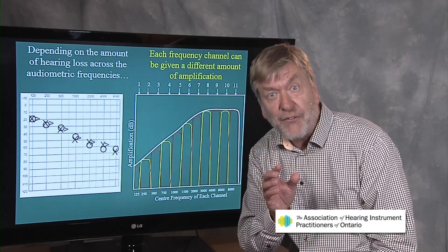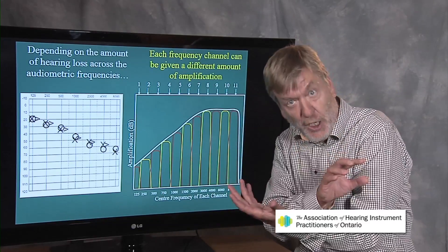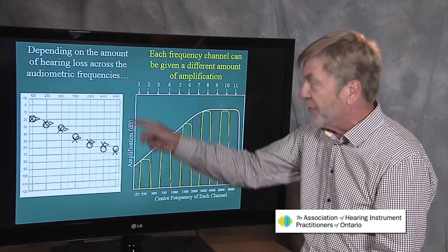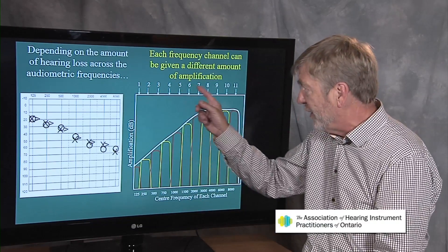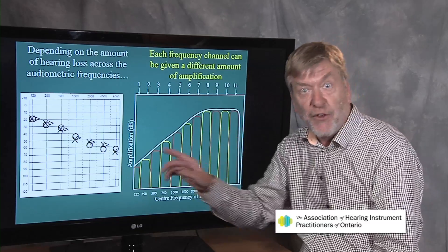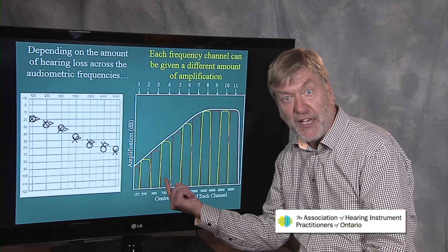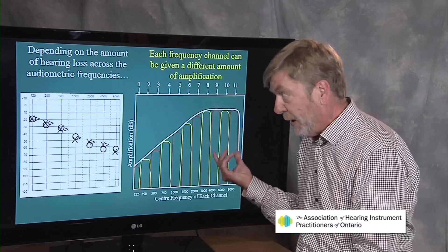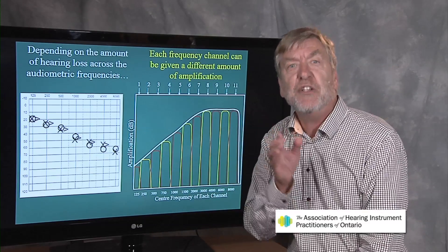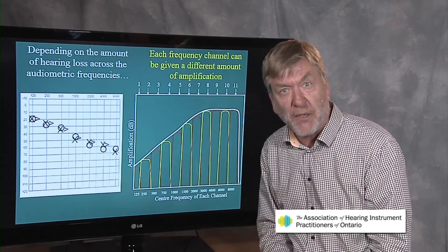A hearing aid for this person should be delivering somewhat of a mirror image configuration — the opposite shape. These are called channels. Frequency is along the bottom and amount of amplification is along the vertical. We can literally lift the amount of amplification we give for this particular person so that it can be shaped much like this. This person is getting very little bass amplification because he's got good bass hearing, and he's getting much more treble amplification because the treble hearing is worse. So hearing aids today are all multi-channel in order to exquisitely sculpt and shape what's called the frequency response of the hearing aid.